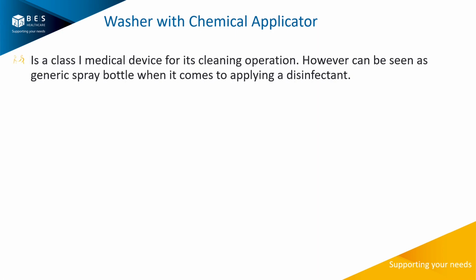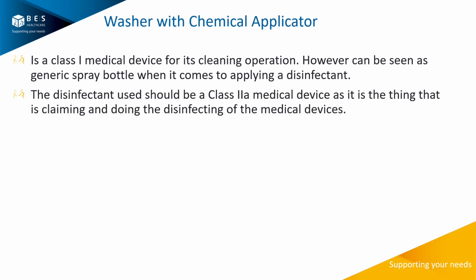And then there are washers which use or apply disinfectants, and this is a little bit more nuanced. So the fact that it is doing cleaning means that the washer in itself as a washer needs to be Class 1. However, the application of the disinfectant can be seen a bit more like our generic spray bottle design. So as long as the machine is not specifically designed to work with a specific disinfectant, then it doesn't make it a Class 2A machine. The disinfectant, because you're applying it to medical devices, does need to be 2A, but the machine does not need to be 2A because it is not doing the disinfecting, it is the chemical that's doing the disinfecting.